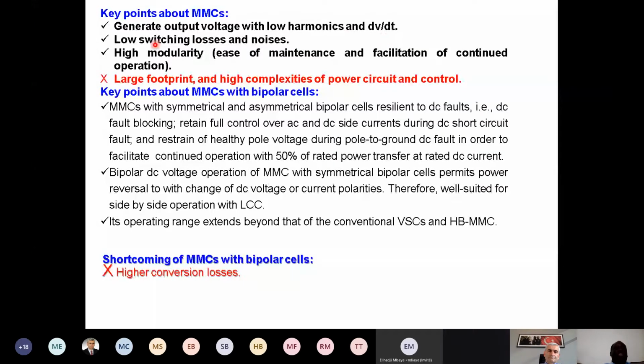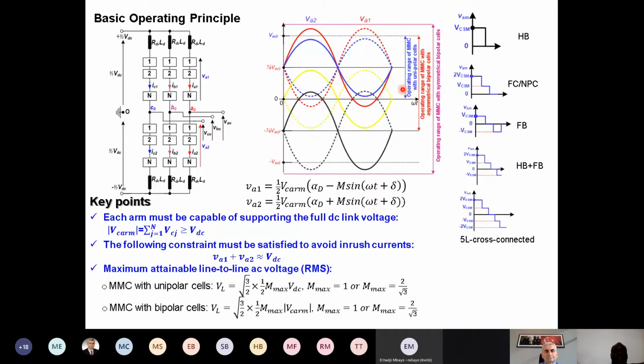And also, it has low switching losses and noise because the devices operate at low frequency, and high modularity made the maintenance much easier, and also made continuous operations much easier. What does it mean? So if you go here, for example, if you lose one of the cells here, you can just bypass these cells and continue to operate. So you can just add extra cells as redundant in case something happens, you just bypass the faulty cells and you continue to operate, which is much more difficult if you have a conventional two-level converter.